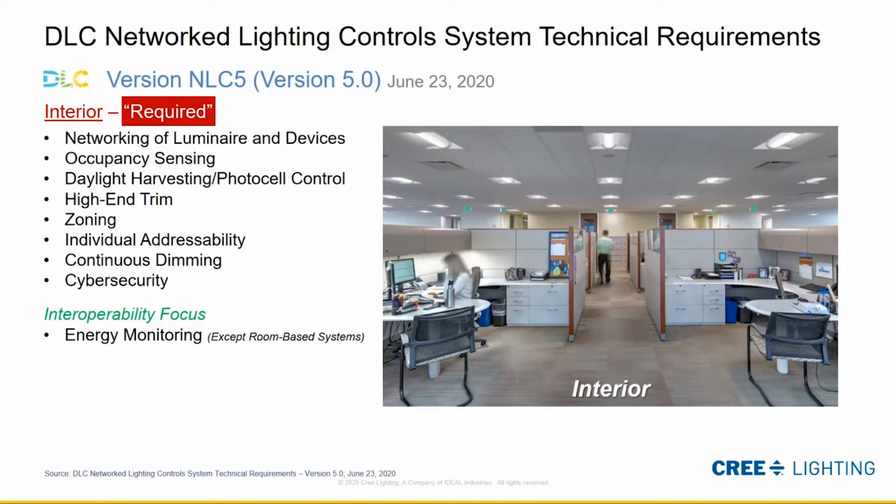Then continuous dimming. Continuous dimming is really seamless dimming, allowing for a good customer experience. There's not that herky-jerky feeling of a step dim where you go from 100% to 50% right away. It's not very satisfying. And certainly in this environment where you have daylight working, you're slowly changing that electric light to adjust with how much daylight is being provided. If it were stepping and jumping, it wouldn't be very satisfying. It wouldn't provide a lot of the energy savings that you would hope.